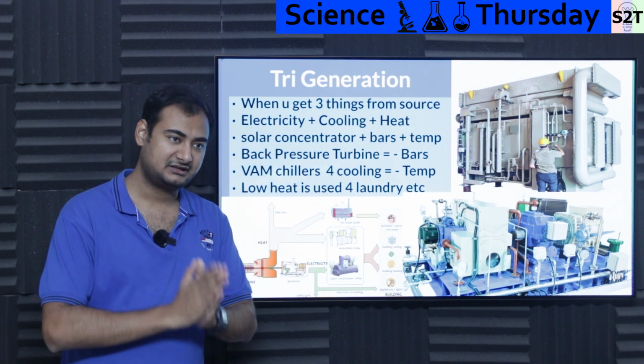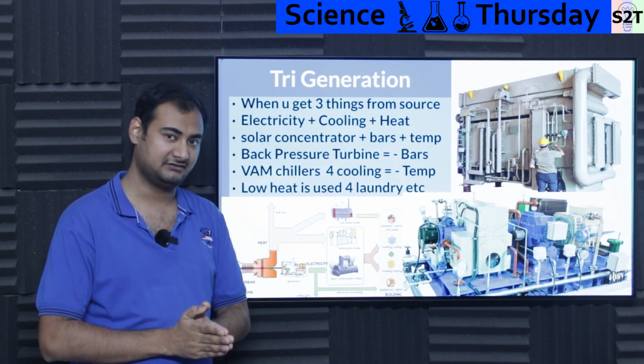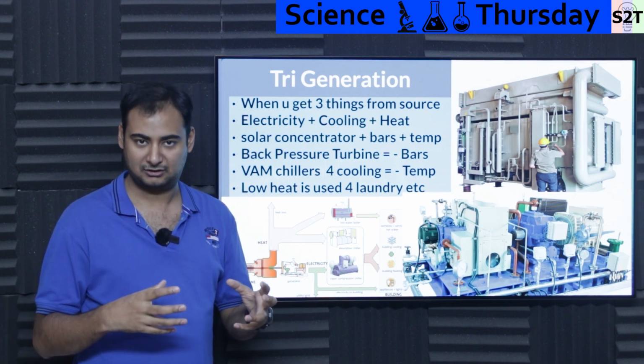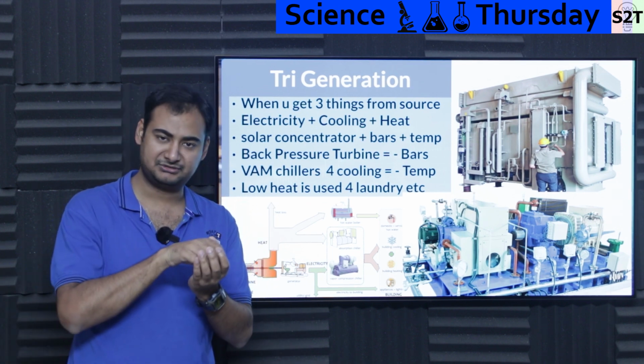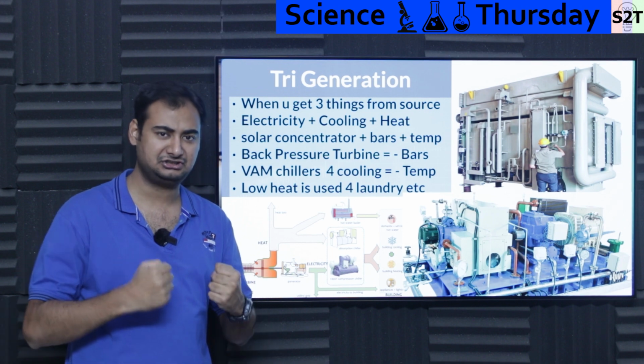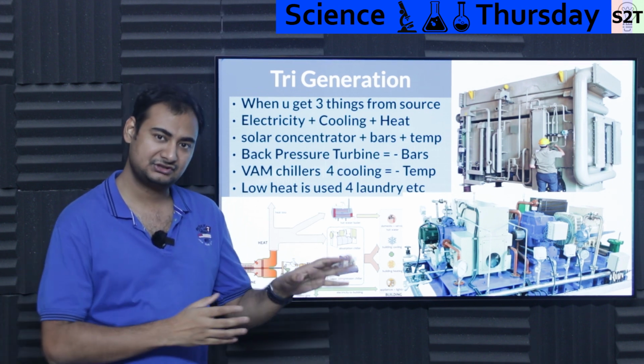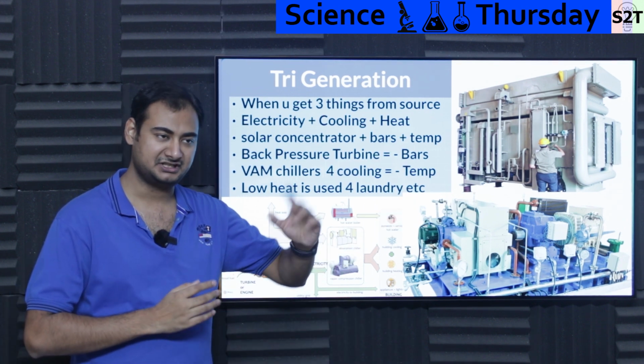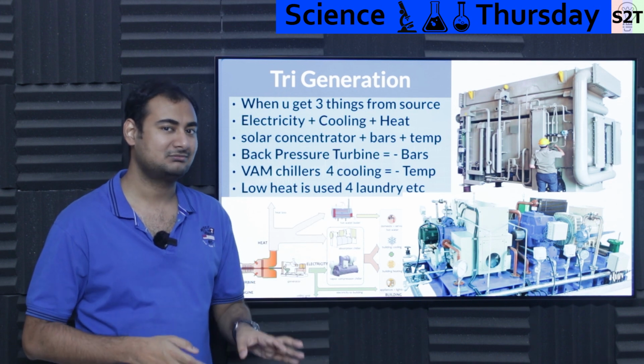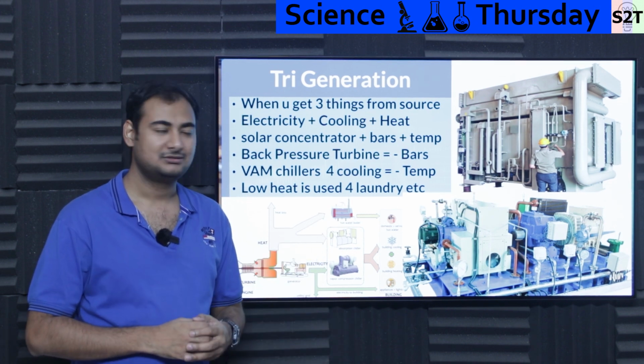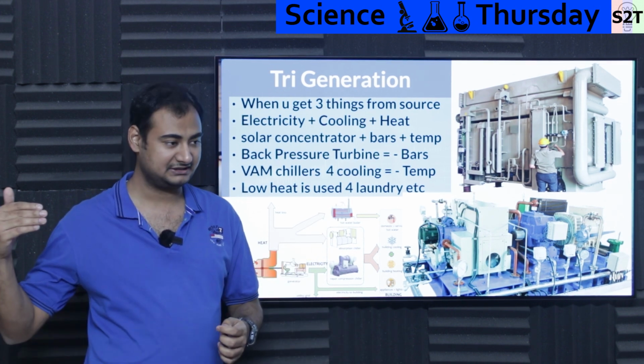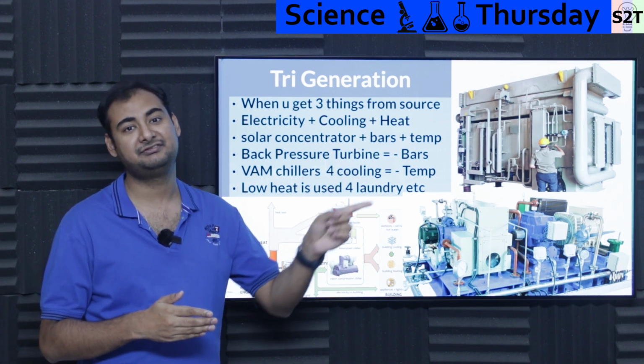Now you have to understand, a turbine is a pressure reducer device, meaning if you look into a coal power plant, the steam pipe is coming in very small, very high pressure, very hot. It goes into the turbine, megawatts of energy come out. But here's the deal, the steam temperature does not drop that much. Of course there is some drop, but not as much as you'd think. If 400 goes in, almost 350 will come out on the other end.